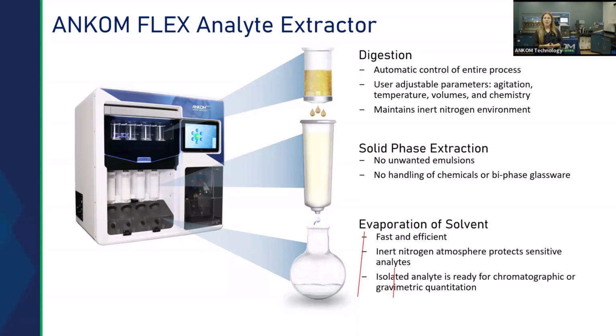Okay, so how do ANKOM instruments handle different types of sample? Oh, I'm sorry, I already answered that one, but there was an addition to it asking if you can do all those samples in one run. The answer is yes, because these are indirect methods. You can run multiple sample types in one run. So if you have 24 samples, say for your fiber run, they can be made up of different sample types and run together. Sometimes for fat analysis, depending on the type of sample, you would maybe just space them out a little bit differently or have a blank bag in between them, but that's only if you suspect maybe some fat leaching to each bag. We don't usually see that.